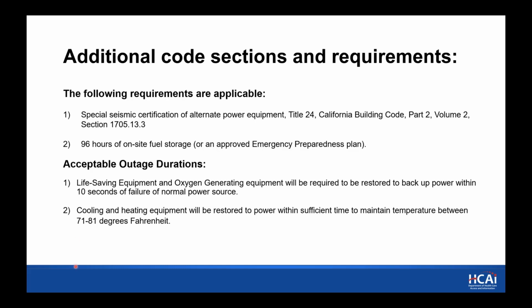Next slide, please. Additional code sections and requirements. In addition to the electrical requirements, the law is very specific that this equipment will remain in operation during natural disasters. So special seismic certification is required for all the new equipment, and 96 hours of on-site fuel storage. So this is above and beyond the electrical code requirements. We've identified the acceptable outage durations as 10 seconds for the life-saving oxygen generating equipment. And for the cooling and heating, it just needs to be restored within sufficient time to maintain the temperatures between the 71 and 81 degree Fahrenheit target.